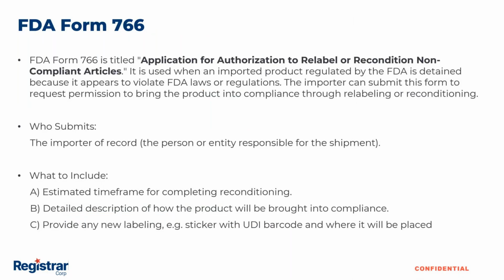Again, talk about Form 766. This is an application for authorization to relabel or recondition non-compliant articles. It is used when imported product regulated by the FDA is detained because it appears to violate laws and regulation. The importer can submit this form to request permission to bring the product into compliance through relabeling or reconditioning. And who submits is the importer of record. What to include? Estimated time frame for completing the reconditioning, a detailed description of how the product will be brought into compliance, and you have to provide a new labeling example showing your UDI barcode and where it is placed in your device.